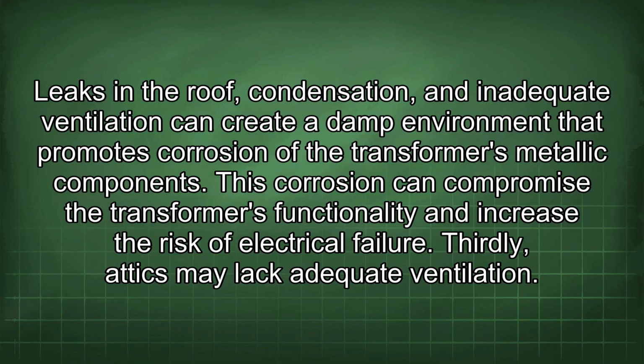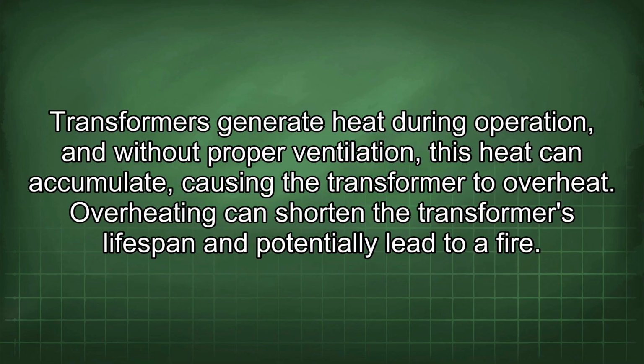Thirdly, attics may lack adequate ventilation. Transformers generate heat during operation, and without proper ventilation, this heat can accumulate, causing the transformer to overheat. The overheating can shorten the transformer's lifespan and potentially lead to a fire.